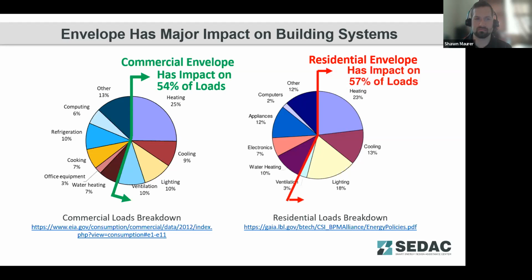And this is just an overview of the impact the envelope has on systems. This isn't a direct envelope energy comparison, but just how much of the building's total energy consumption the envelope impacts overall. In commercial buildings here, heating systems, cooling systems, lighting and ventilation are all impacted by the envelope. So that's about 54% of the building's loads. It varies back and forth a little bit depending on your climate zone and your building design. But essentially every component of the building that isn't plug loads, lighting, or other miscellaneous loads like appliances is impacted by the envelope of the building. And so having that primary focus there early in design is going to do the most for reducing overall energy consumption.